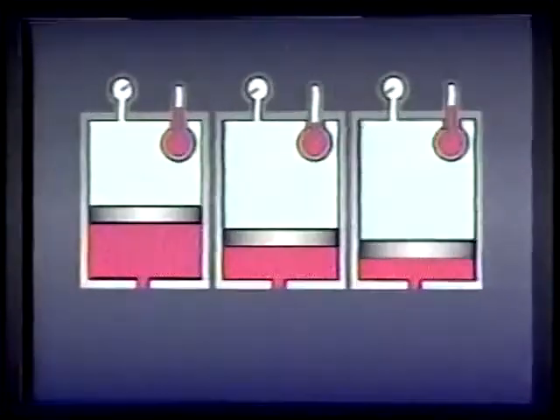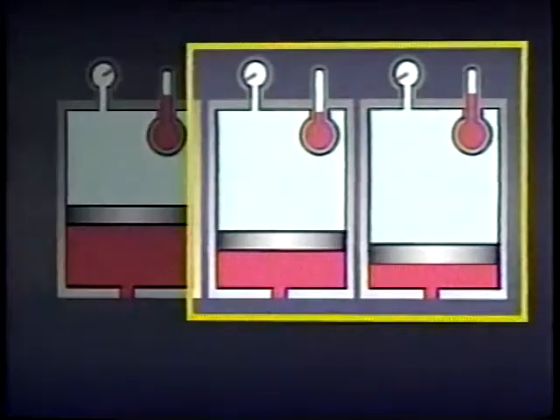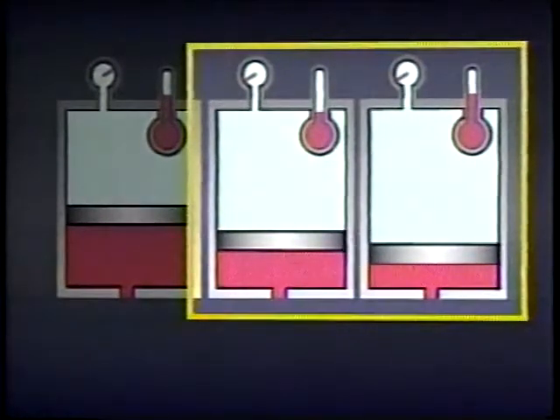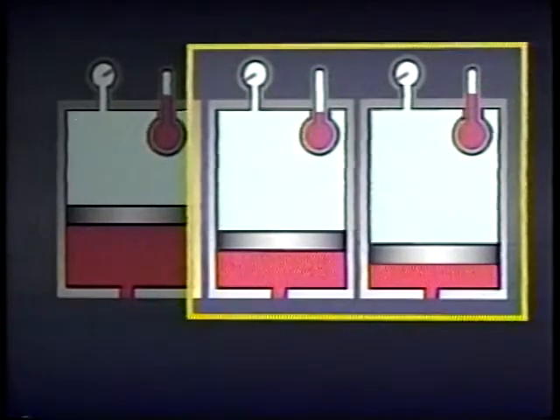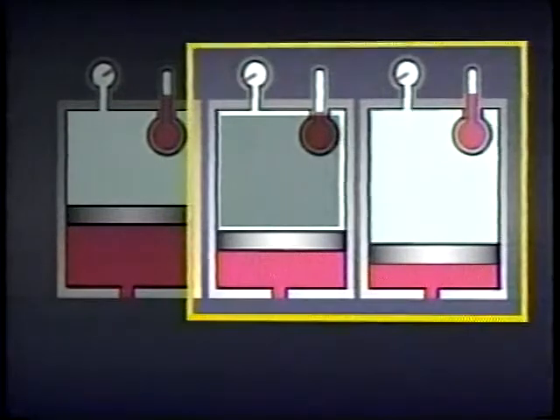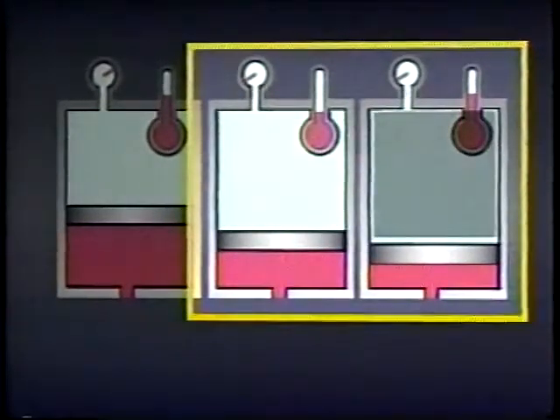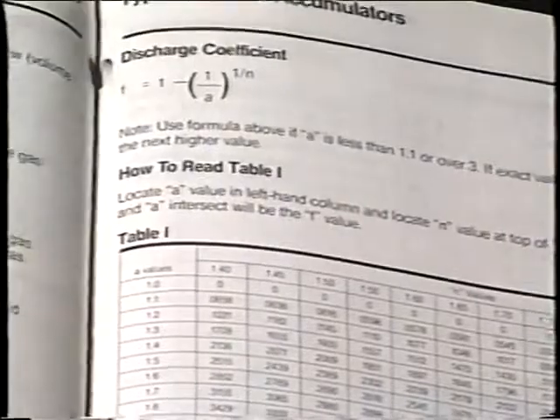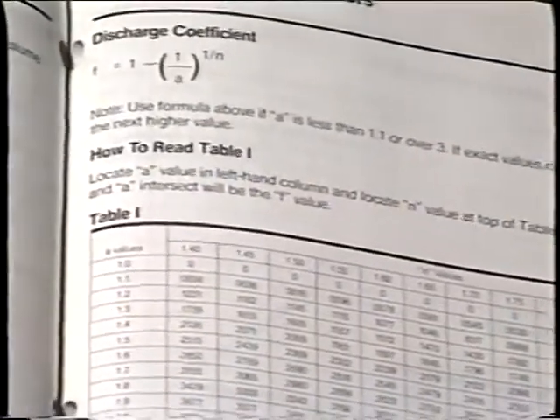Discharging fluid from an accumulator can also be done adiabatically or isothermally, and the effect on usable volume is very similar. When fluid is discharged rapidly, less fluid is released because the pre-charge doesn't have time to expand as much as it would have if the accumulator had been discharged more slowly. The other factor that affects accumulator performance is the pressure of the pre-charge.